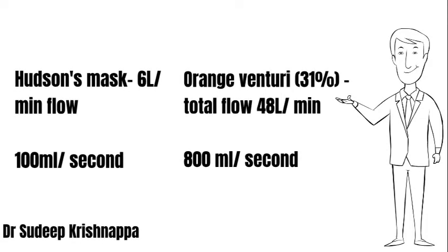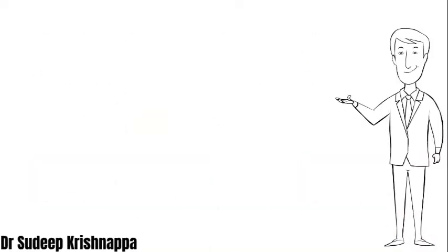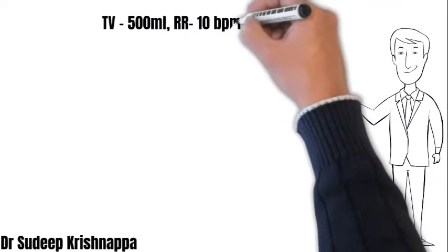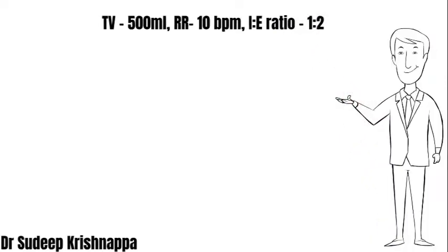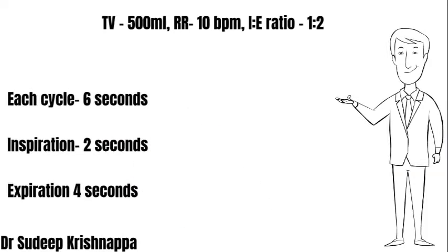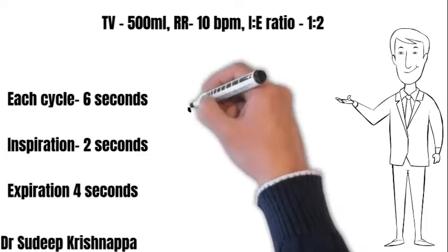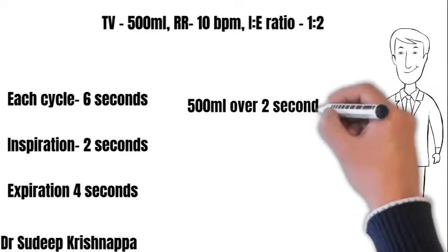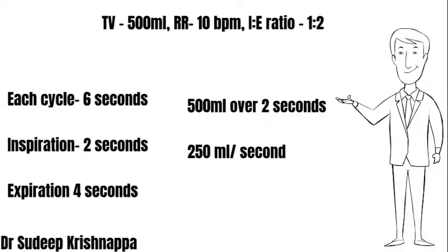The first scenario: a person breathing a tidal volume of 500 mL, respiratory rate of 10 breaths per minute, I:E ratio of 1:2. With 10 breaths per minute, each respiratory cycle is 6 seconds. With an I:E ratio of 1:2, the 6 seconds are divided in the ratio 1:2, giving an inspiratory duration of 2 seconds and expiratory duration of 4 seconds. With uniform inspiratory flow, the tidal volume of 500 mL flows in over 2 seconds, amounting to 250 mL per second.